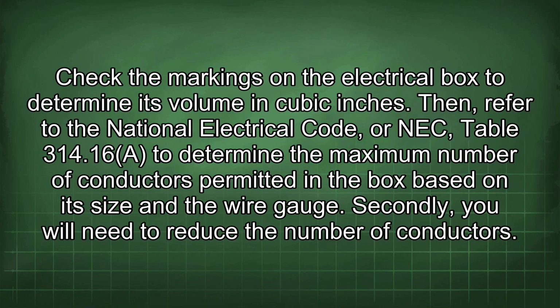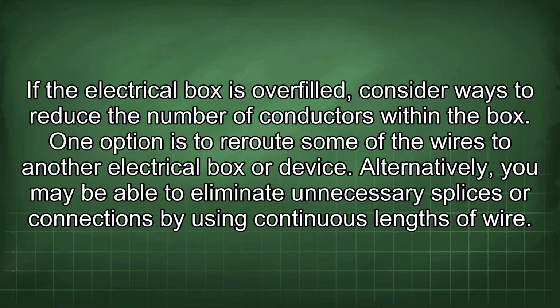Check the markings on the electrical box to determine its volume in cubic inches. Then, refer to the National Electrical Code, or NEC, Table 314.16 to determine the maximum number of conductors permitted in the box based on its size and the wire gauge. Secondly, you will need to reduce the number of conductors. If the electrical box is overfilled, consider ways to reduce the number of conductors within the box. One option is to route some of the wires to another electrical box or device. Alternatively, you may be able to eliminate unnecessary splices or connections by using continuous lengths of wire.